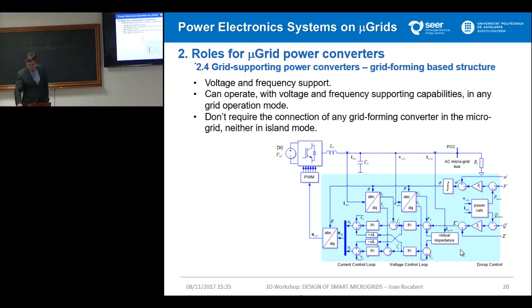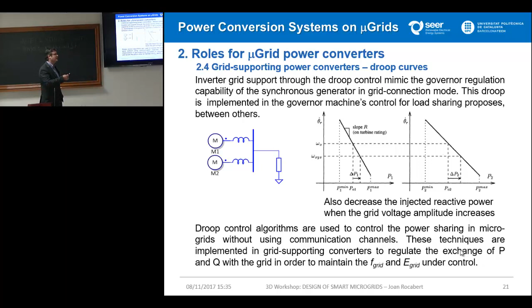The droop curves, as you know perfectly, are a concept coming from the machines, from the synchronous machines. Synchronous machines can easily be operated in parallel thanks to those droop curves. Each converter, like each machine, gets its own droop curves. When the grid is working at some specific frequency, this determines how much power each one of the converters should give, as the synchronous machines do. If we get a change in the power, or a change in the impedance of the microgrid, a new operating point is determined according to those curves, and the sharing of the power is performed with those droop curves.